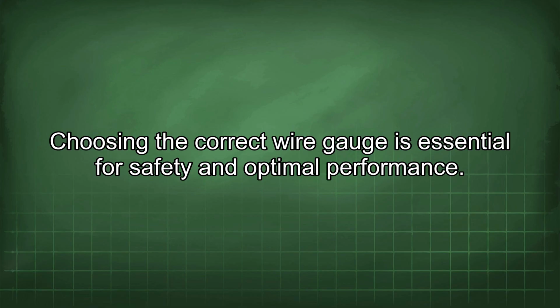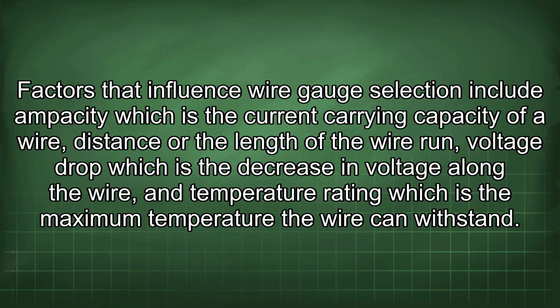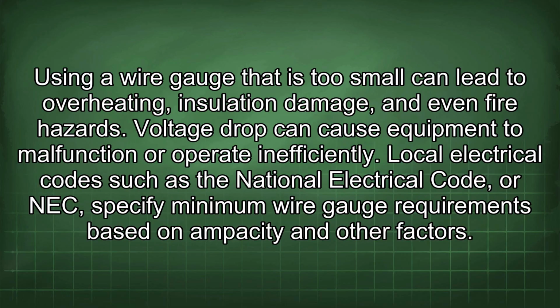Choosing the correct wire gauge is essential for safety and optimal performance. Factors that influence wire gauge selection include ampacity, which is the current carrying capacity of a wire, distance or the length of the wire run, voltage drop, which is the decrease in voltage along the wire, and temperature rating, which is the maximum temperature the wire can withstand. Using a wire gauge that is too small can lead to overheating, insulation damage, and even fire hazards. Voltage drop can cause equipment to malfunction or operate inefficiently.